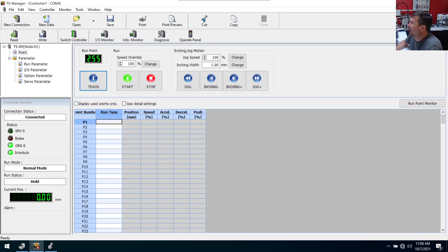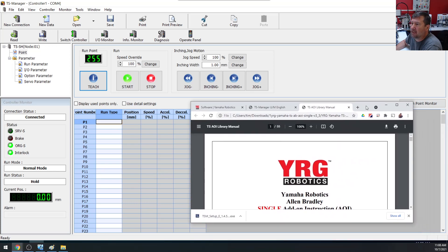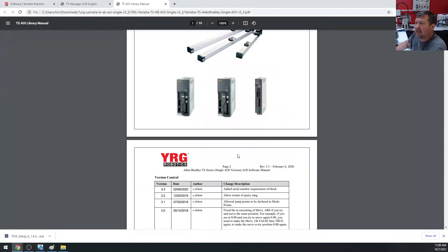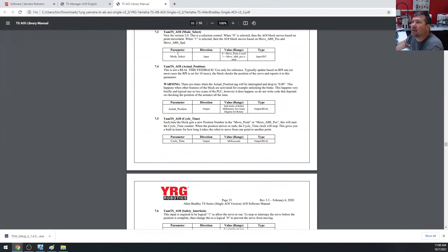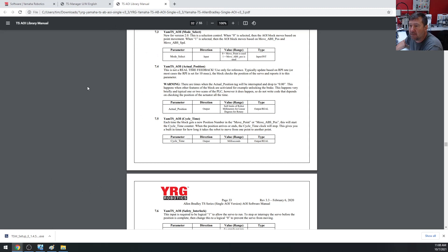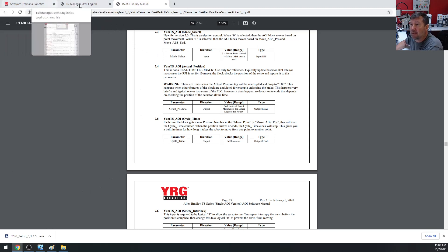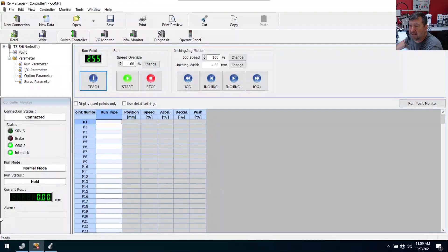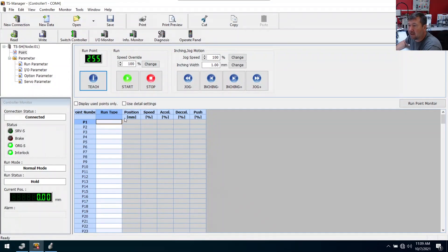I remember that in the AOI - mode select when set to zero, the AOI block moves based on point movement. When it's one, it moves off absolute position and speed. So if we just wanted to simplify our logic or didn't want to deal with the headaches of figuring out all the numbers in the Compact Logix, my guess is we can just program them right here.